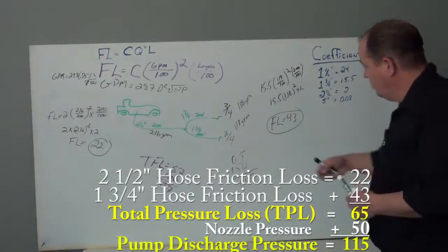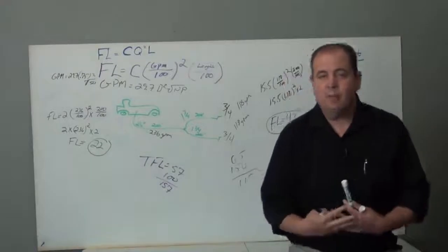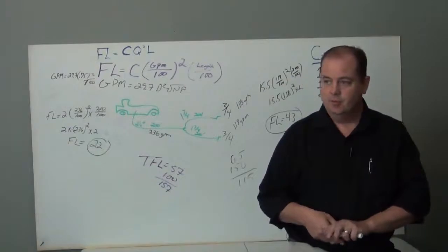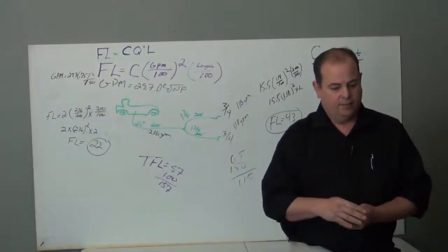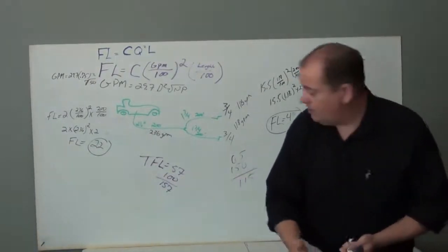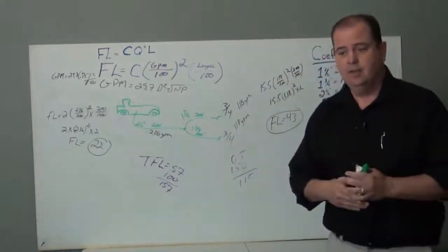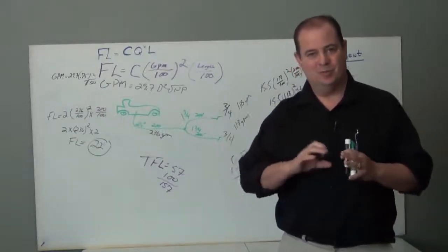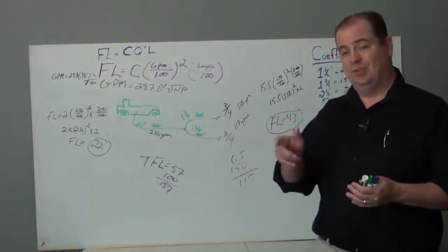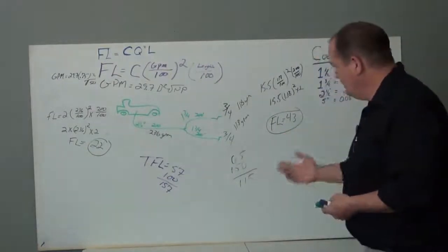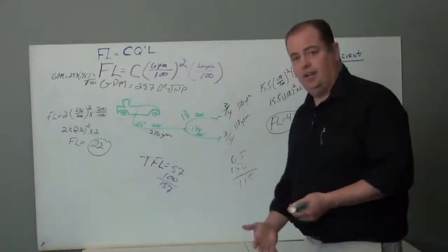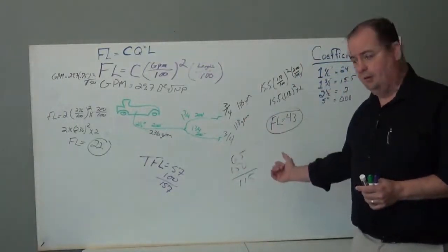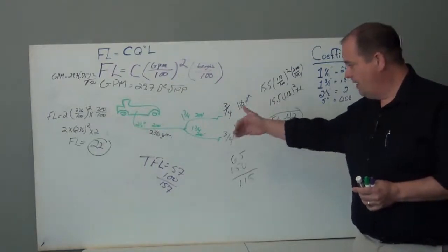So here's the scenario where we had combination nozzles flowing 110 gallons. We're flowing 220 roughly, but let's just keep it simple, 110 per line. And we had to set our pump to 157. Now, some people's SOGs years ago, our pressure relief valve was supposed to be set at 150, so 157 is not doable. You had to, of course, crank it up. Now, if we use smoothbore tips, we can set it at 115. That's a huge difference from going from a combination nozzle to a smoothbore.